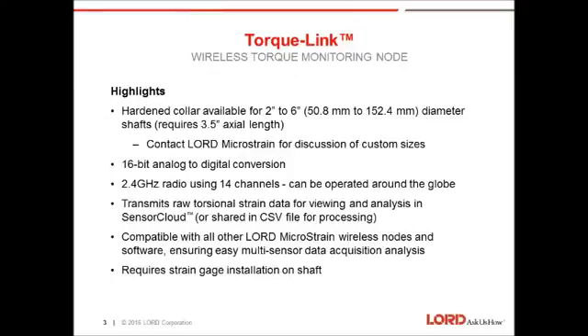The Torque-Link does require strain gauges to be installed on the shaft. We believe that most customers will have this capability in-house. If they do not have this capability, we could potentially install strain gauges for a customer, but that's going to be a custom quote based on the job, volume, complexity of the installation, things of that nature.